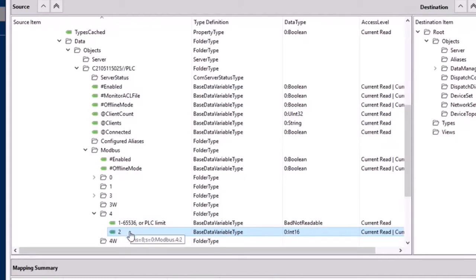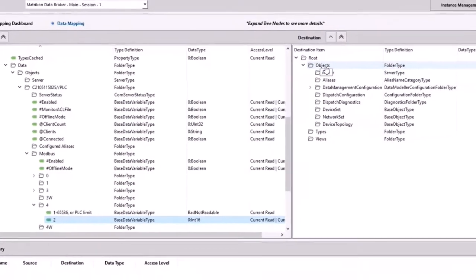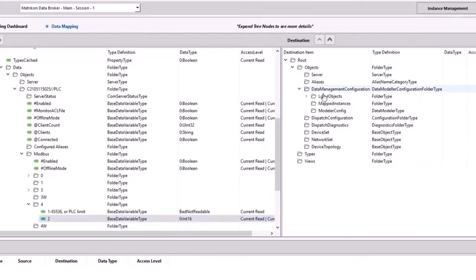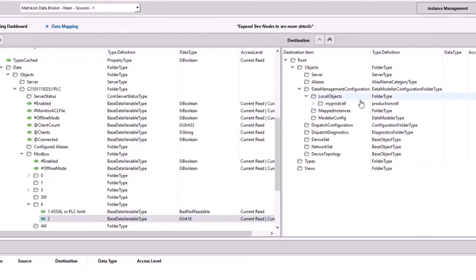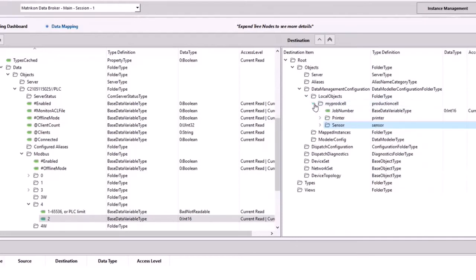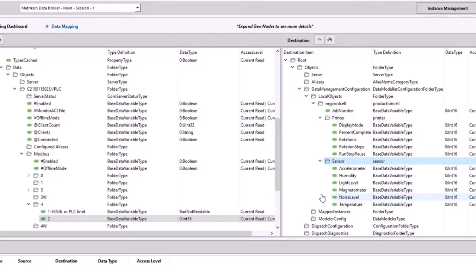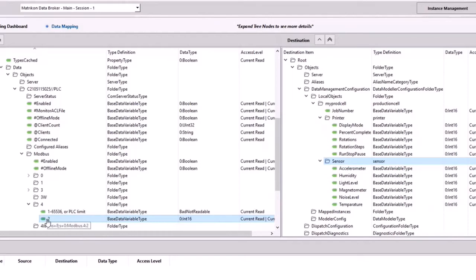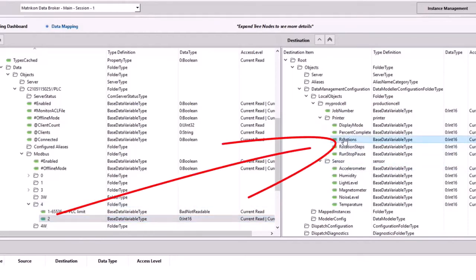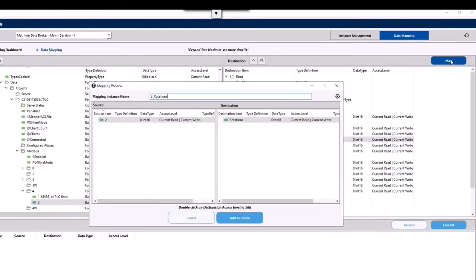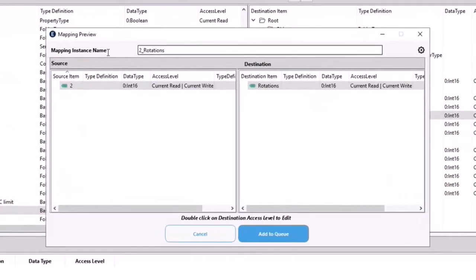So I've highlighted our 4 colon 2 register on the Modbus side, and now I'm going to expand objects, expand data management configuration, and then local objects. And this is where our instances are contained for Data Broker, and you'll see lo and behold we have my prod cell which we created earlier, and underneath we've got the printer and sensor tags. So in this case I want to map plant Modbus 4 colon 2 into rotations. So I highlight both, left side source, right side destination, and click map. A window will appear, you have the option of changing the instance name, by default it will appear as is, but you do have the option to change that, and you can click add to queue.